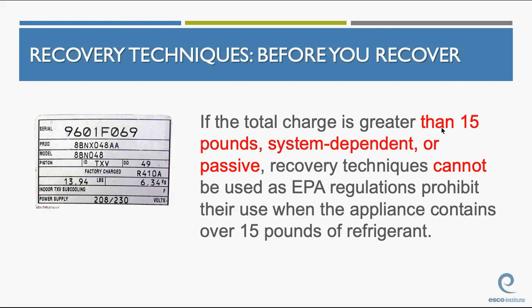If the total charge is greater than 15 pounds, system-dependent or passive recovery devices cannot be used, as EPA regulations prohibit their use when the appliance contains over 15 pounds of refrigerant. The majority of residential systems, the majority of commercial systems are running over 15 pounds of refrigerant. You don't want to use a passive recovery device in this situation. So if the total charge is greater than 15 pounds, you cannot use passive recovery.